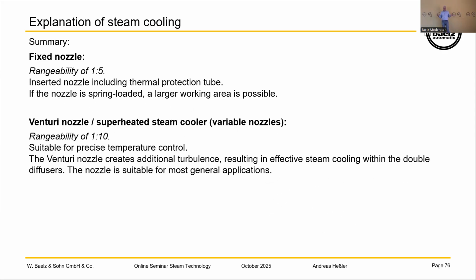The next system would be the Venturi system. We have here a rangeability of 1 to 10. It is for a good temperature control. The Venturi nozzle creates additional turbulence, and as an effect, it cools down the steam much better than just a normal spray nozzle.